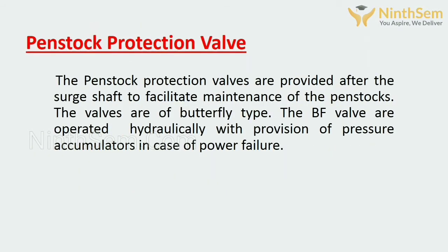Penstock protection valve. The penstock protection valves are provided after the surge shaft to facilitate maintenance of the penstock. The valves are of butterfly type. The butterfly valves are operated hydraulically, with provision of pressure accumulator in case of power failure.